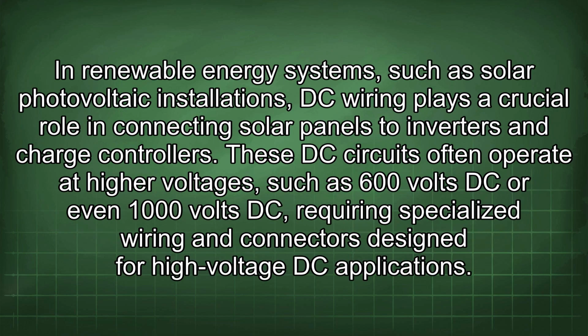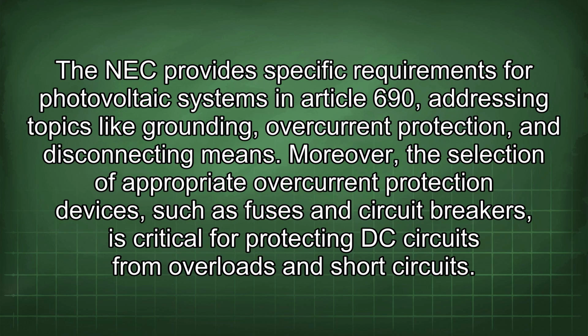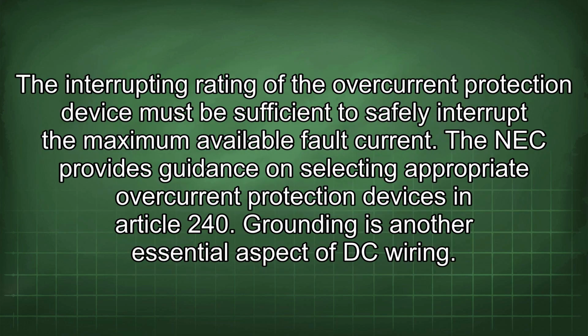In renewable energy systems, such as solar photovoltaic installations, DC wiring plays a crucial role in connecting solar panels to inverters and charge controllers. These DC circuits often operate at higher voltages, such as 600 volts DC or even 1000 volts DC, requiring specialized wiring and connectors designed for high-voltage DC applications. The NEC provides specific requirements for photovoltaic systems in Article 690, addressing topics like grounding, overcurrent protection, and disconnecting means. Moreover, the selection of appropriate overcurrent protection devices, such as fuses and circuit breakers, is critical for protecting DC circuits from overloads and short circuits. The interrupting rating of the overcurrent protection device must be sufficient to safely interrupt the maximum available fault current. The NEC provides guidance on selecting appropriate overcurrent protection devices in Article 240.